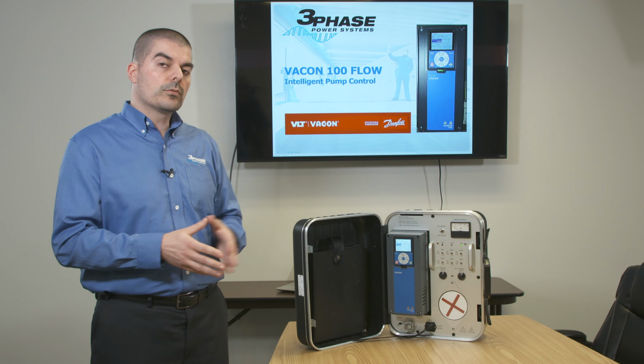Any chance, an opportunity, an application we have, VACON 100 Flow is definitely the way to go. Hardware and software is just second to none. The mean time between failures is about 57 years on these drives. They're phenomenal. The DC bus capacitors, we have the EMI RFI filters, the varnished boards, the fact that we have 690 volt drives, so that means that the diodes and the transistors are rated for higher voltage capacitance and tolerance. The DC thin film capacitors, if they get hit by transients, they actually do not get hot spots like the electrolytic capacitors, they actually self-heal.